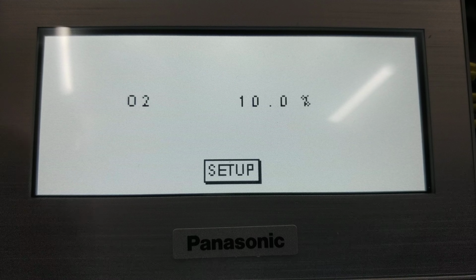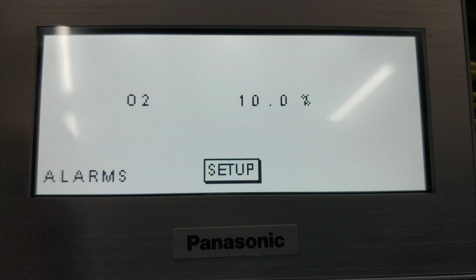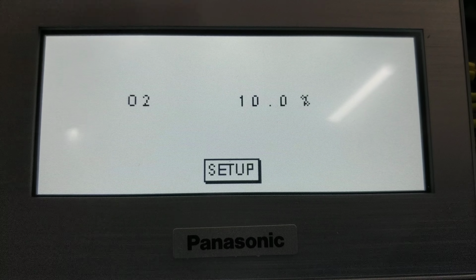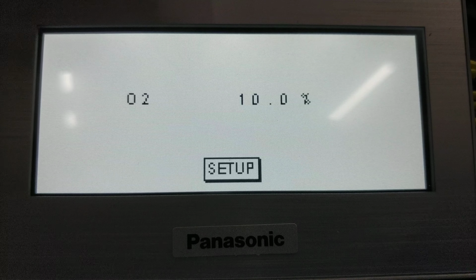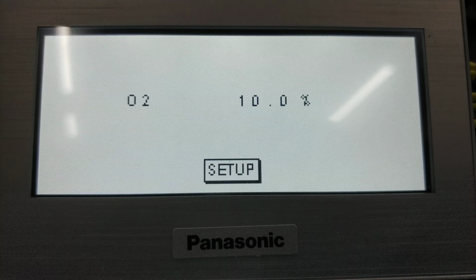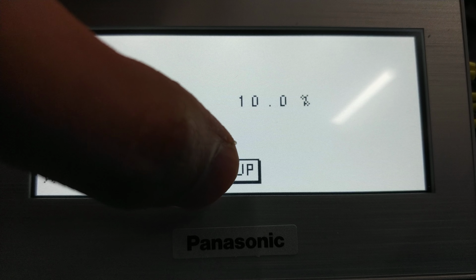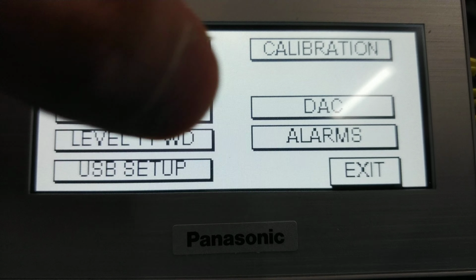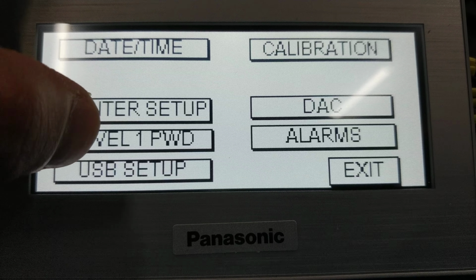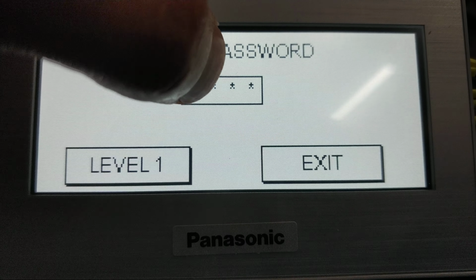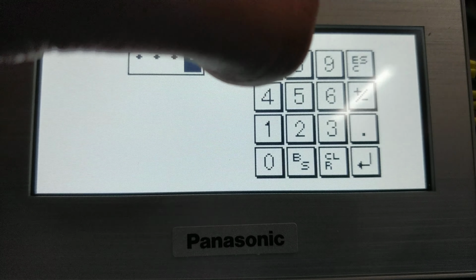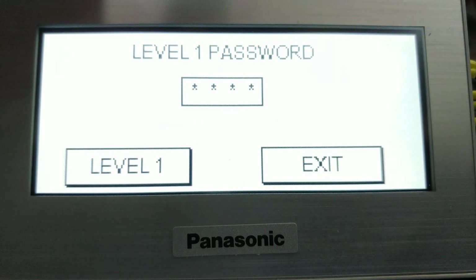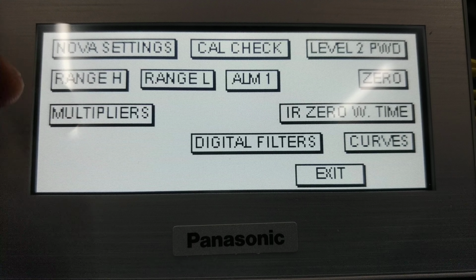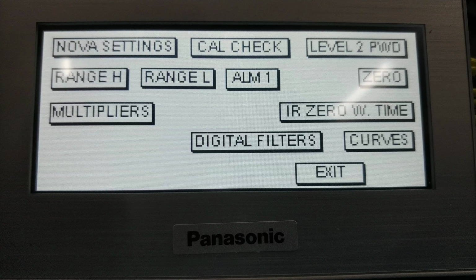We're still getting a high gas alarm because we're reading above 2%. So what we're going to do now, if we want to change the set point, is go into the level 1 password and do that for the gas alarm. So we're going to go to setup, level 1 password. To level 1, password is 270 again, 270, enter, and now there's only one gas alarm, we want to pick that, and it's going to be ALM1, this one right here.